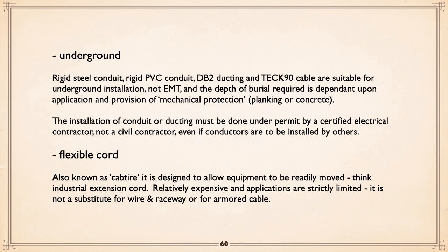Now we talk about underground, and I mentioned PVC, rigid steel, DB2 ducting, TECK90 cable are suitable for underground, not EMT. And the depth of burial is dependent upon provision for mechanical protection, which is in the electrical code.